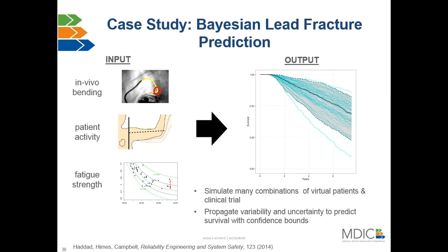And then not only that, but we have to understand how a patient moves. Just because they're implanted in a severe case where there might be a lot of damage to the device, if they move their arm, they may not move their arm very much. They may be an old, frail person that really is not moving their arm, and you need to have both of those combinations to really get a failure. So we have to understand the activity level as a function of our implant population.